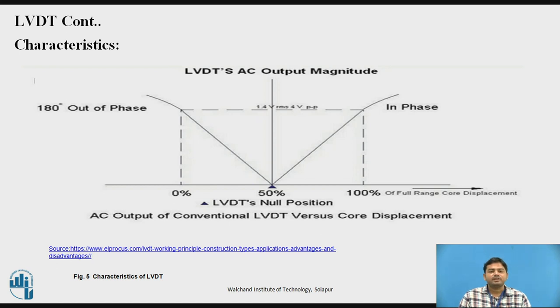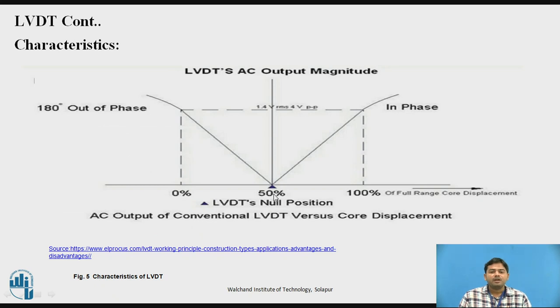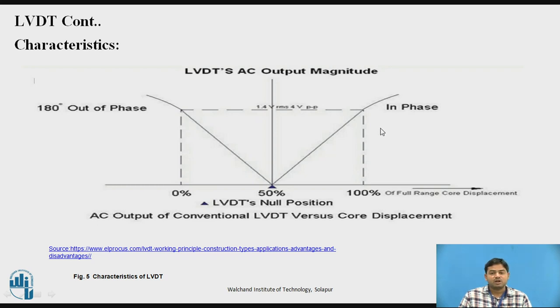Coming to the characteristics of the LVDT: at the null position the differential output is zero. During motion either upward or downward, when considering the magnitude of the output — not the phase shift — the output is linear. That is why this device is called 'linear.' This linear output corresponds to full deflection, or full scale value, in one direction, and the output in the opposite direction has a 180-degree phase shift.